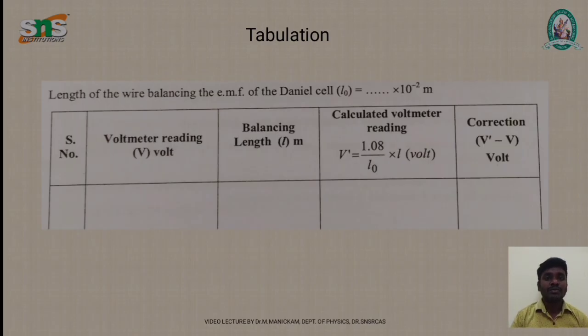This is the tabulation for the low range voltmeter potentiometer: the voltmeter reading and the balancing length. We calculate the voltmeter reading using the formula V dash equals 1.08 divided by L naught, into L. This is the V dash calculation. Then we find the correction, V dash minus V.